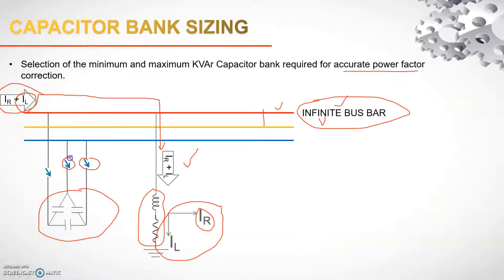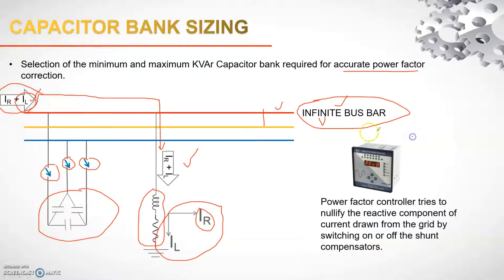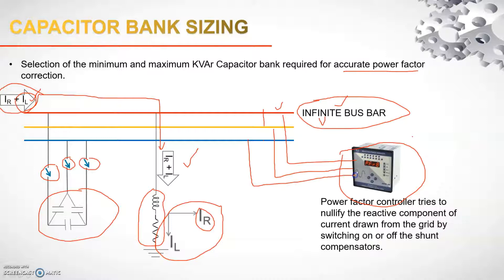The capacitor bank, though connected to the grid through switches, is initially disconnected. Depending on the current IL, the capacitor bank will be connected to the grid by command from the power factor manager or reactive power manager. This manager has all data from the grid — current and voltage data from the CT and auxiliary coils — and continuously monitors the system power factor.